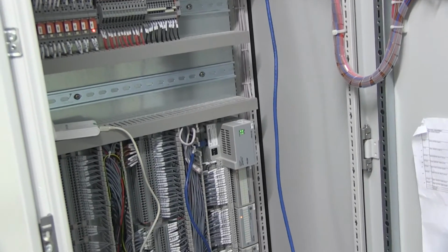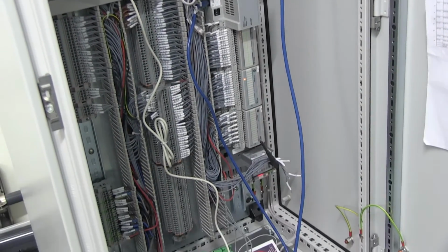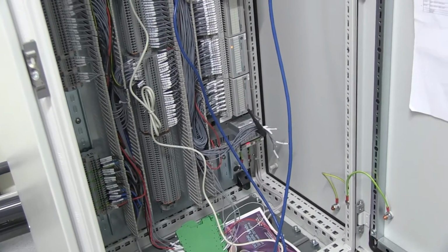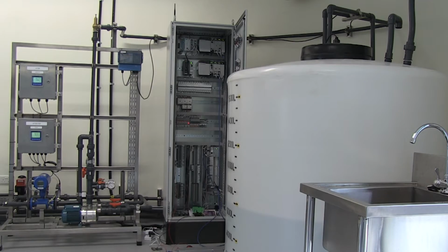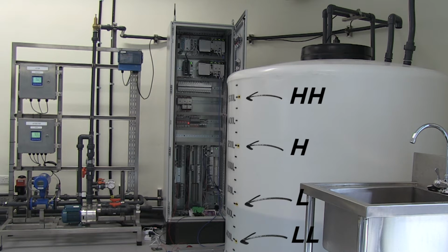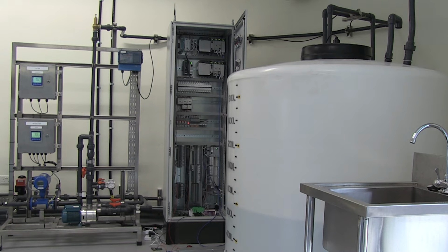The purpose of the controller at stage 1 is to manage the flow of raw water from the inlet to stage 2. Water flows into tank T101 when the motorized valve located behind the tank is opened. Water flows out of the tank to stage 2 when this constant speed pump is turned on. Tank 101 is marked with 4 level indicators: HH, H, L, and LL. These visual indicators correspond to numerical values of water level in T101 and are used by the PLC to control the valve and the pump.